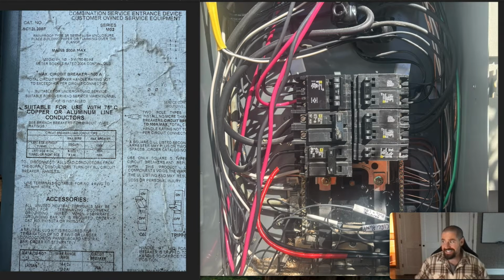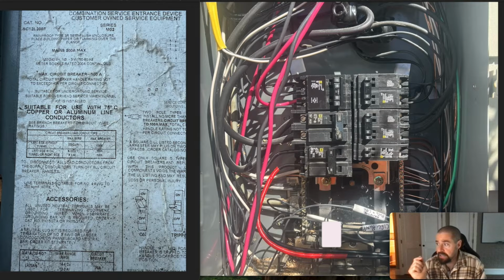So first, what is a hot bus panel? A hot bus panel is a main service panel that does not have a main breaker coming in from the utility. Essentially, it has two bus bars that come in on each leg, as you see here on the bottom right, that are just always hot coming in from the utility. Those are your service conductors, and it just has a hot bus in the middle there that is built to contain up to 6 double pole circuit breakers.